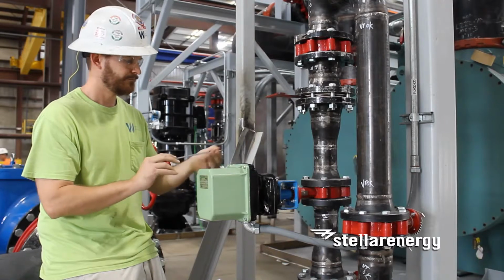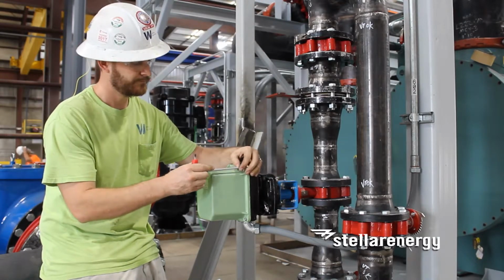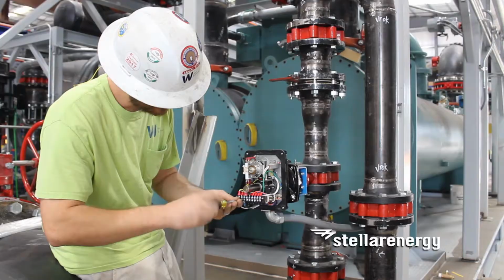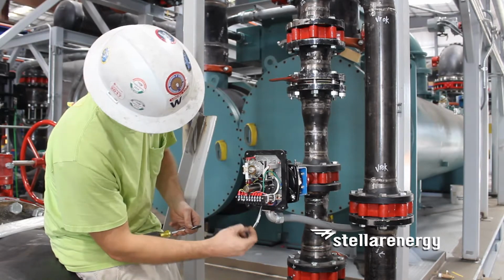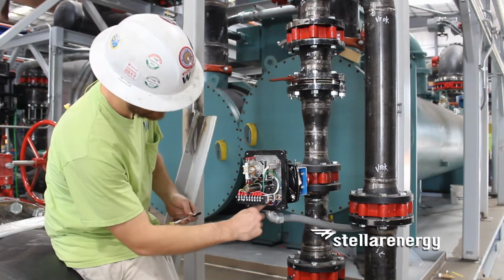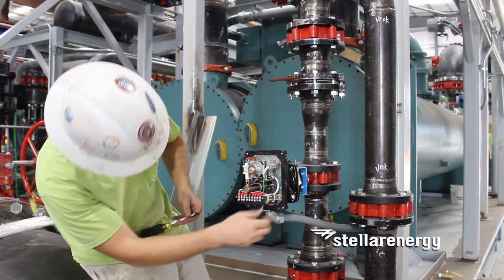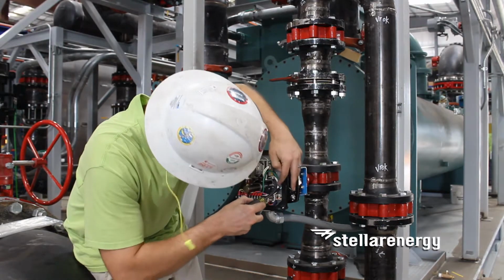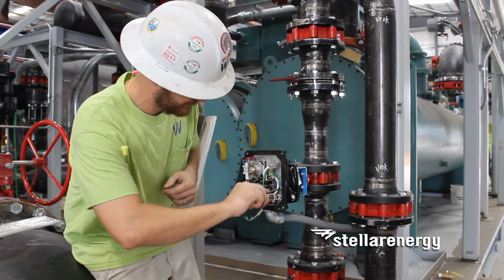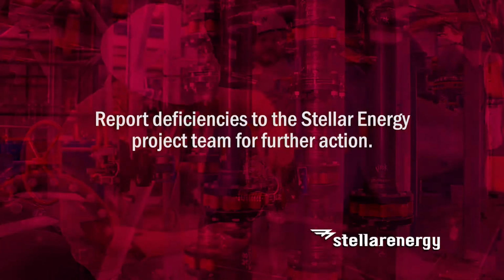All electrical cables that were disconnected for shipping purposes will be pulled and terminated by the site contractor. After termination, all of the electrical and controls cables should be properly inspected and tested to verify that no damage occurred during the shipping or installation processes. Any deficiencies noted by the site contractor should be reported to the Stellar Energy project team for further action.